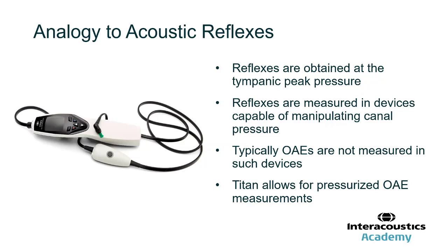This also requires a system that is capable of manipulating the ear canal pressure, which is typically not a system that OAEs are embedded within. And fortunately for us, we have a device in Interacoustics, the Titan, which can measure OAEs and also manipulate ear canal pressure. It's a happy marriage between the two.